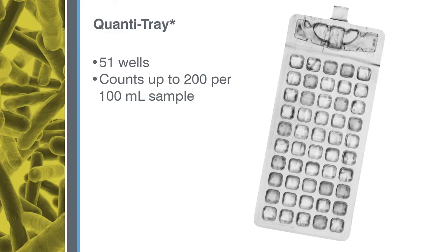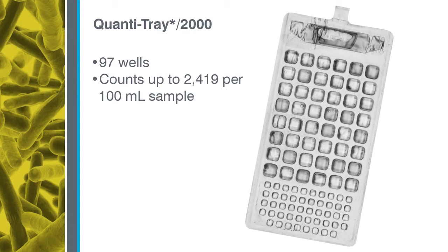IDEXX offers two sizes of QuantaTray. Both work with the QuantaTray sealer. The standard QuantaTray is a disposable 51-well tray that provides counts up to 200 per 100 ml sample without dilutions. The QuantaTray 2000 is a disposable 97-well tray that provides counts up to 2,419 per 100 ml sample without dilutions.